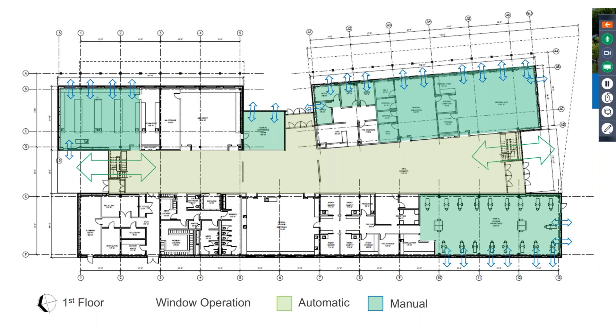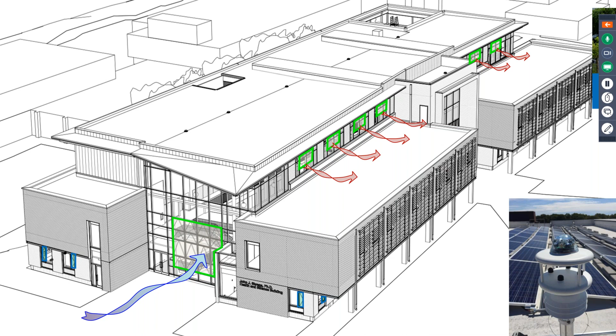So very tight building. On the opposite end of the spectrum, we also have natural ventilation. Now that may seem odd for a building that has a lot of laboratory space in it, but we did not apply it in chemical use areas that have fume hoods, but we applied it in many of the other areas. You can see here on the first floor, in blue arrows show all of the manually operable windows, including the dental clinic and nursing arts, CLS teaching spaces. And then there's the central atrium space, and that's a fully automated system with motors that actuate the windows. And you can see here a diagram of the flow taking advantage of wind and buoyancy in the atrium space. We have a weather station on the roof that then tracks the outdoor air conditions to determine when it's appropriate to open the windows.